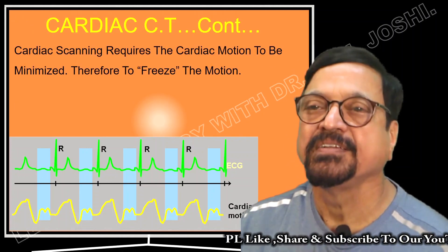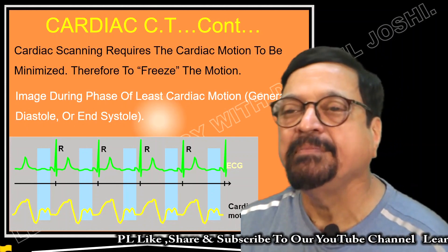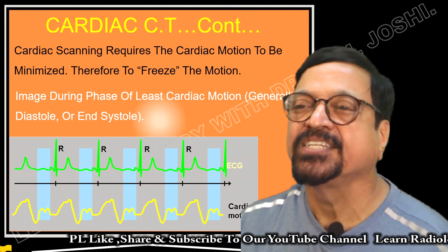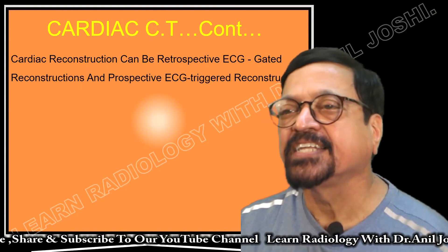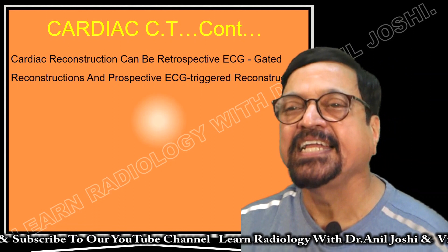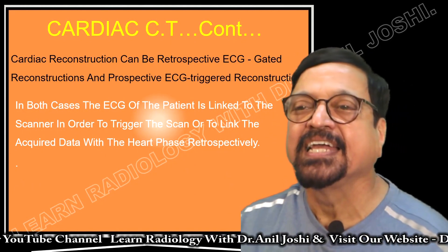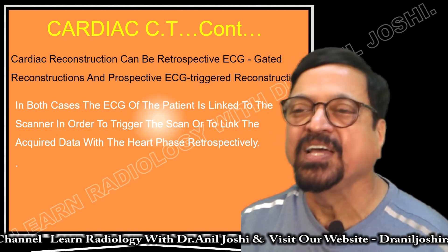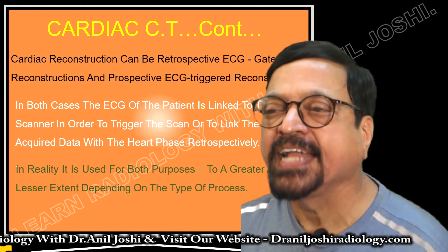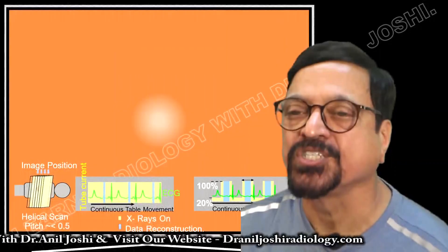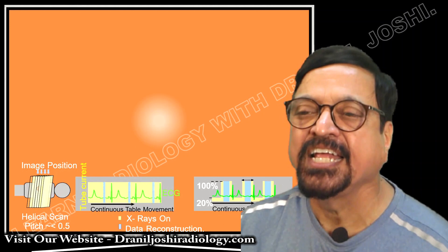Cardiac scanning requires cardiac motion to be minimized — to freeze the motion. The image during the phase of least cardiac motion is generally achieved during diastole or end-systole. Cardiac reconstruction can be retrospective ECG-gated reconstruction or prospective ECG-triggered reconstruction. In both cases the ECG of the patient is linked to the scanner in order to trigger the scan and link the acquired data with the heart phase retrospectively.